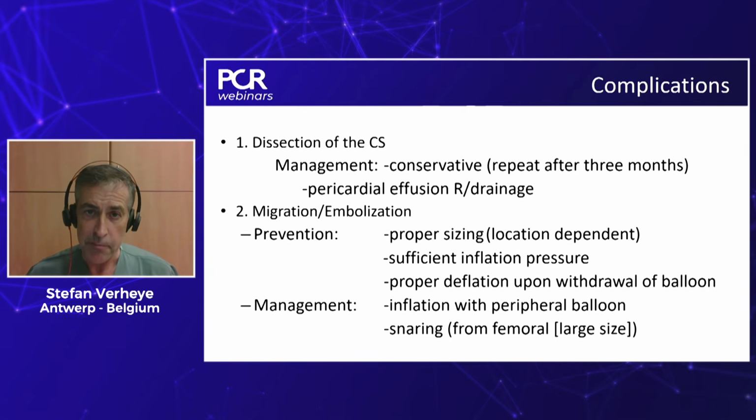What do I mean by that? Migration: you've seen it's a rather bulky device, and it's not like a stent mounted on a balloon. It's a little bit bigger, and therefore it's not that well secured or safe on the balloon. So be careful, and never exit it from the guiding unless you want to implant it and retract the guiding. So that's important.